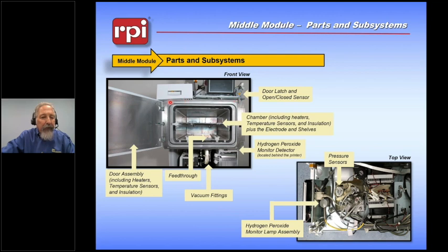Back on the cursor again. There we go, on the laser pointer. So we have a gasket that seals the chamber. Also the door, flat surface to make sure we don't have any leaks. We have an inner chamber, which is electrically conductive, and it's connected to our RF supply using a feed through that is electrically insulated from the outer parts of the chamber.